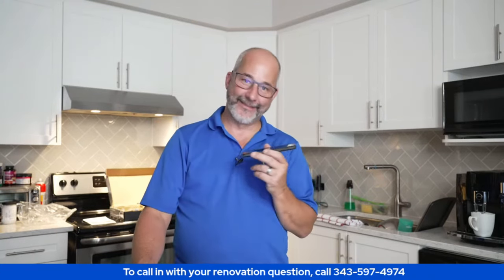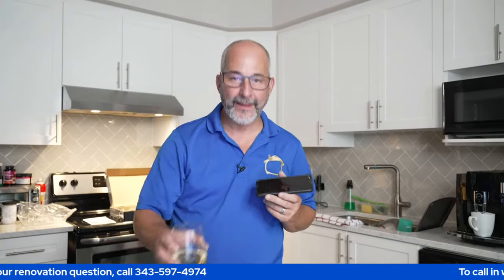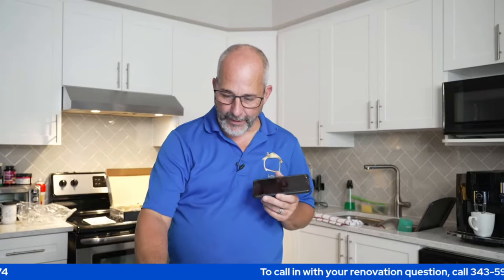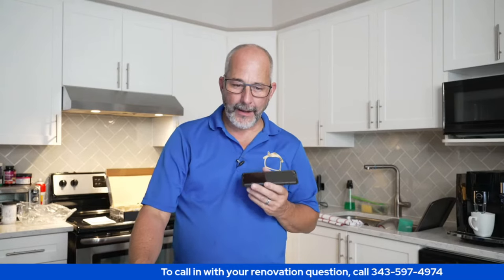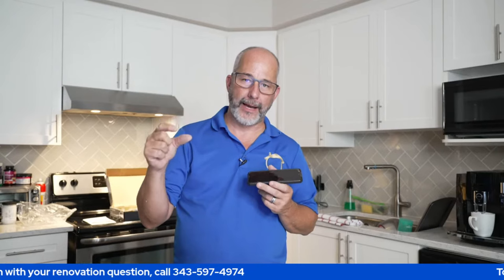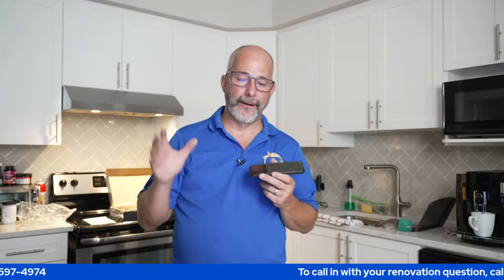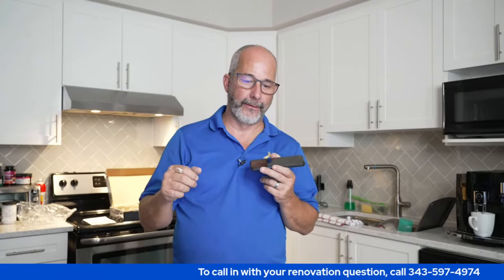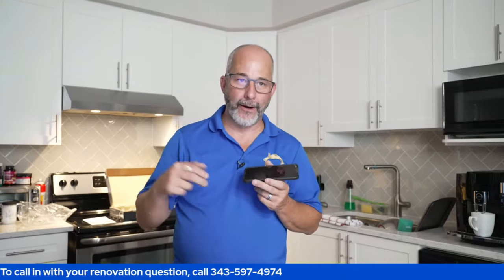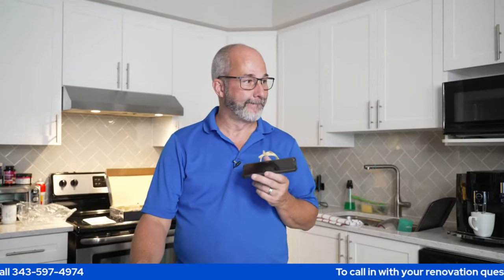Well, but what if I'm unable to figure out a way, what if I put a GFCI in that HVAC outlet? Yeah, the problem with that is you're going to make the plug safe, but you're not going to make the constant power and the wiring safe. And so you could start a fire inside the wall. And at the end of the day, if you're doing your own electrical in Florida, you still need to get a permit anyway, wink, wink. So there's no way to work around that. You're going to have to open up the wall enough to get access and put in the grommet, my friend.